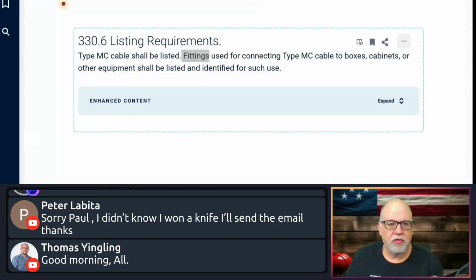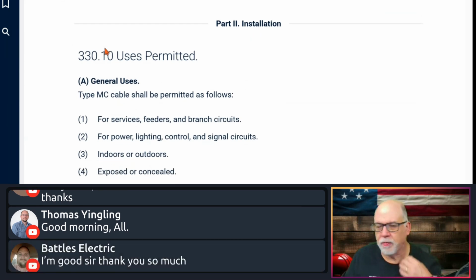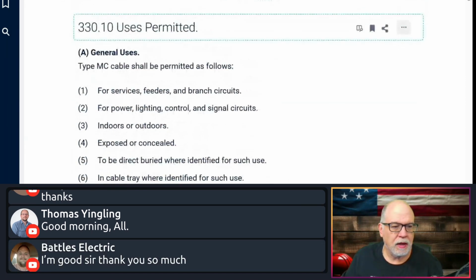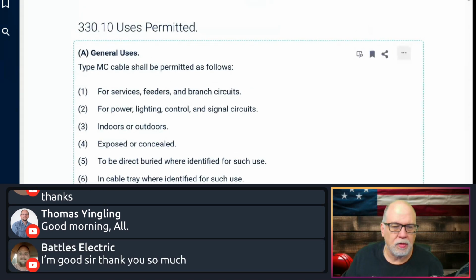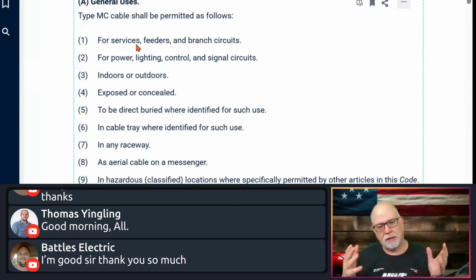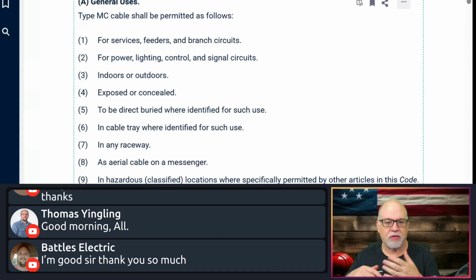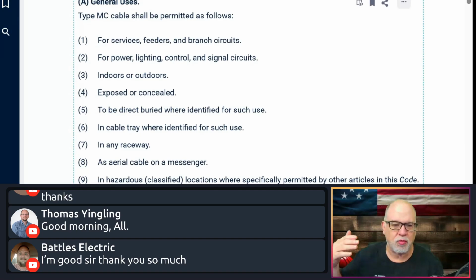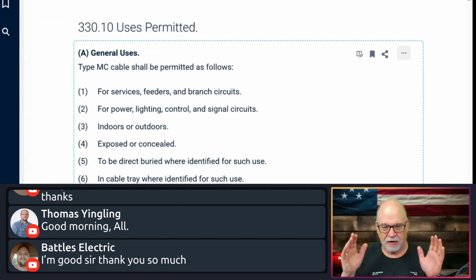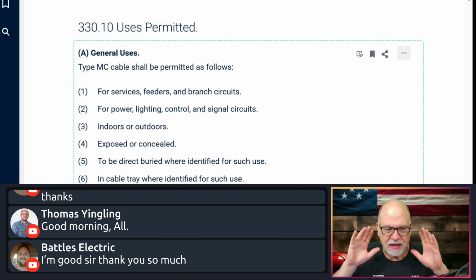All right, so that's the listing requirement. Uses permitted. Where can you use MC cable? Remember, this is talking about general MC right now. It's not specific to interlocked, smooth, corrugated, or continuous weld. We see continuous weld used a lot in hazardous location applications where interlock wouldn't be used. But at the end of the day, this general requirement, uses permitted, is very general. It's not talking about any one specific type.